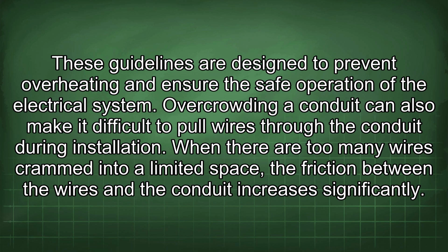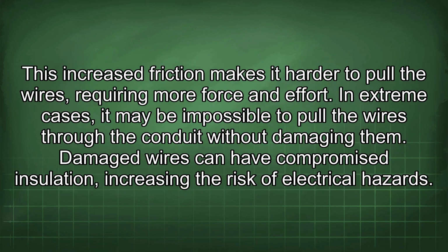Overcrowding a conduit can also make it difficult to pull wires through the conduit during installation. When there are too many wires crammed into a limited space, the friction between the wires and the conduit increases significantly. This increased friction makes it harder to pull the wires, requiring more force and effort. In extreme cases, it may be impossible to pull the wires through the conduit without damaging them. Damaged wires can have compromised insulation, increasing the risk of electrical hazards.